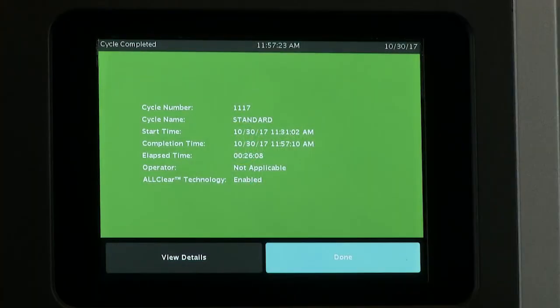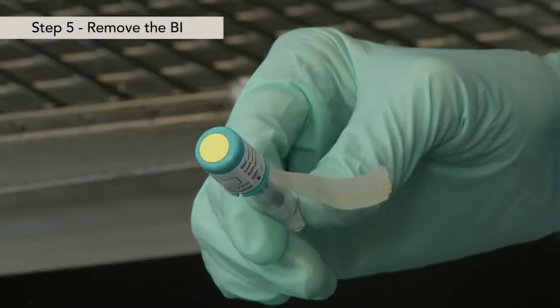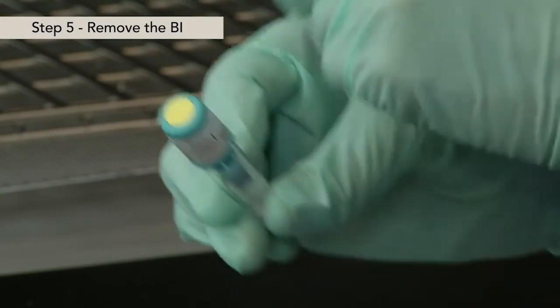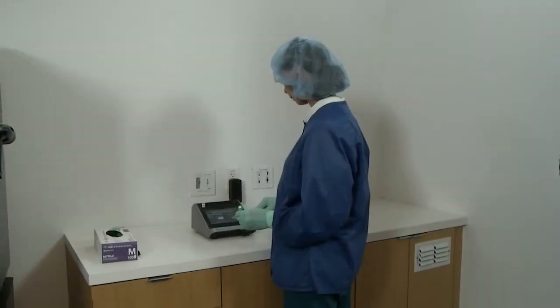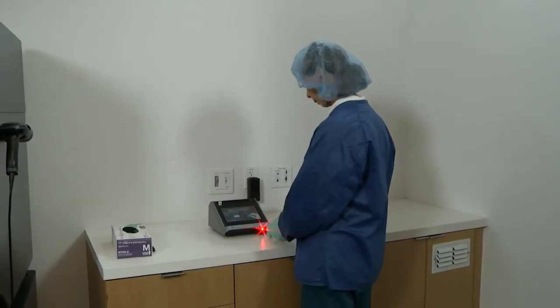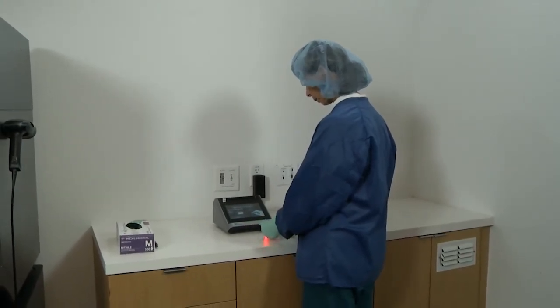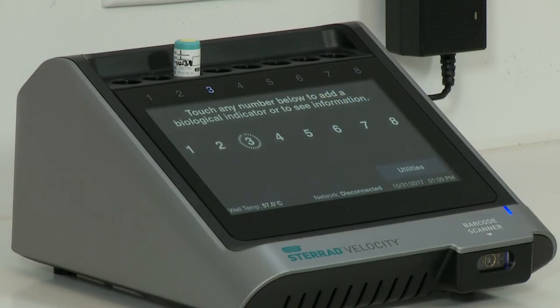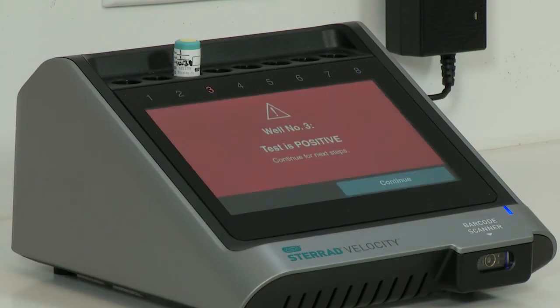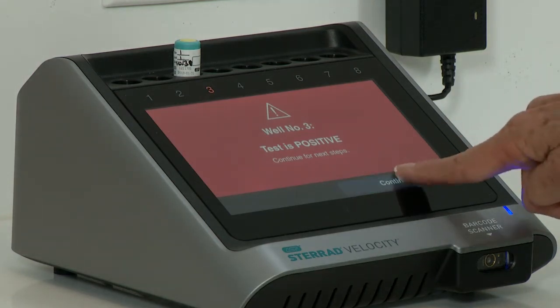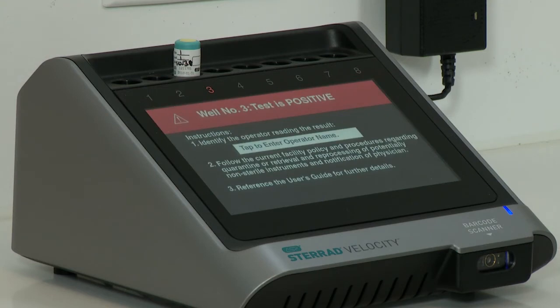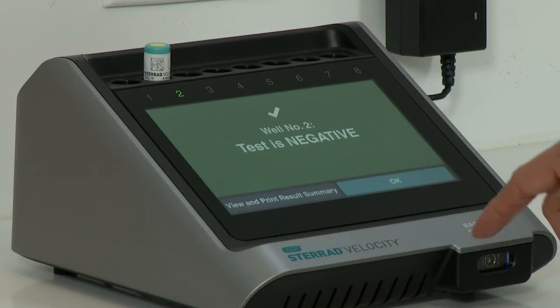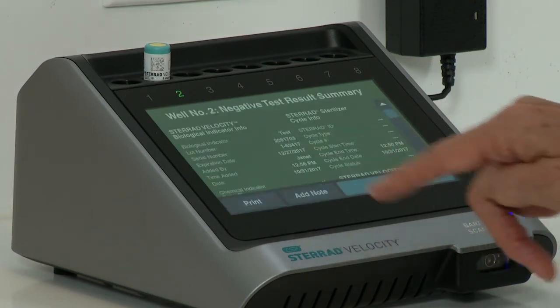Step 5. Once the cycle completes, put on protective gloves and remove the BI from the chamber. The BI must be placed in the STERRAD Velocity reader within the time frame specified in the instructions for use. The system will ask the user to contact an ASP representative if the reader detects 2 out of 3 test biological indicators are positive. You will continue to receive this warning after each sterilization cycle completion until 2 consecutive STERRAD Velocity test BIs are negative.